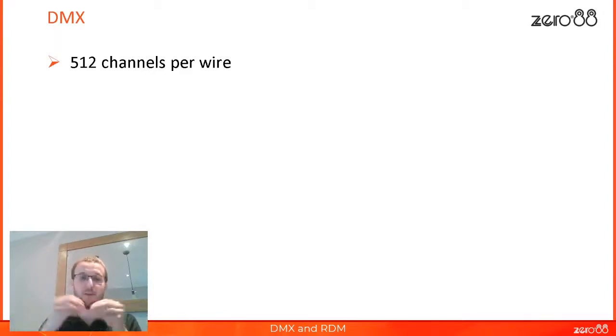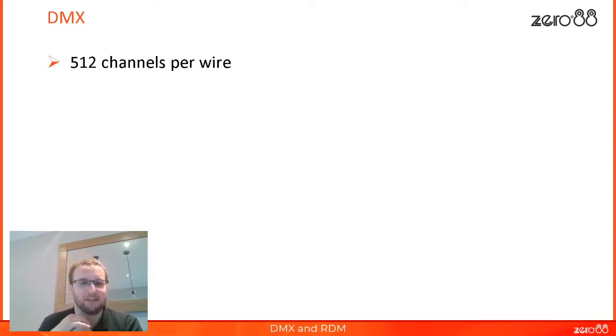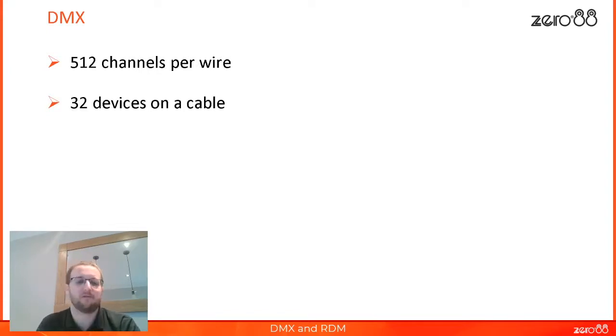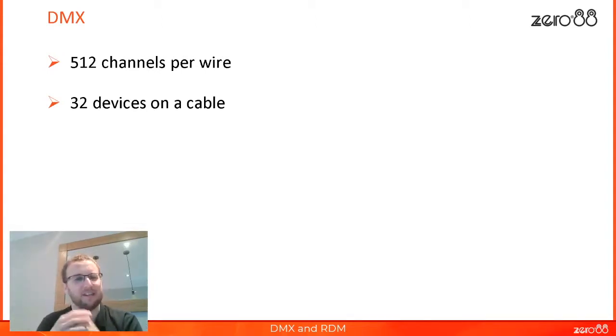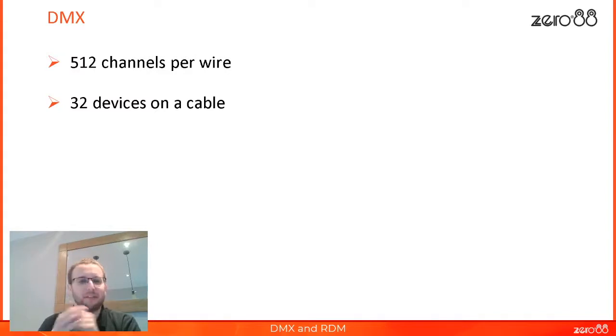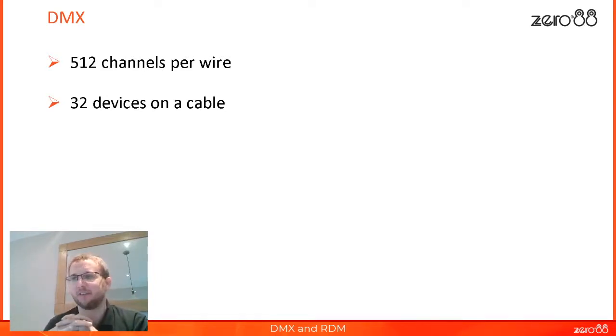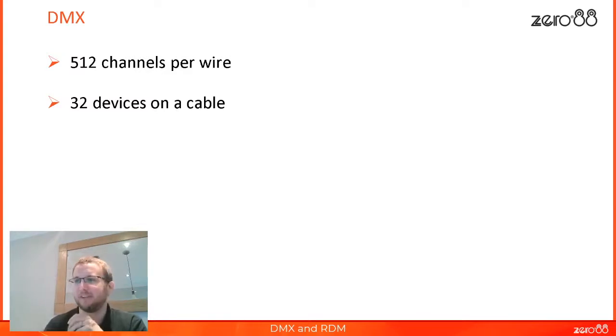You run a second cable for your second universe, or a third, or a fourth. You can easily get into the hundreds of universes on larger setups. On each cable, the official rule is 32 devices. Equipment is much better quality nowadays and you can generally go above 32 without too much of an issue, but officially it's 32. Unlike the 512 channels — which is set in stone — you can't get 513 channels down a cable, but you could happily have 33 or 34 devices.